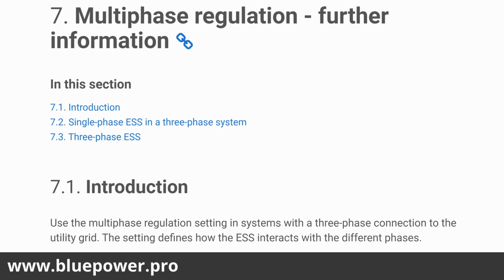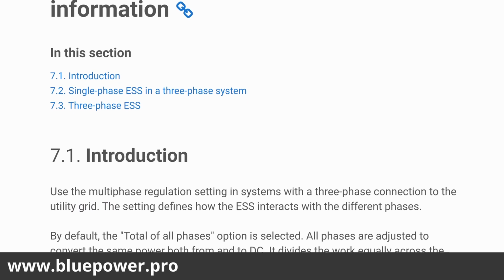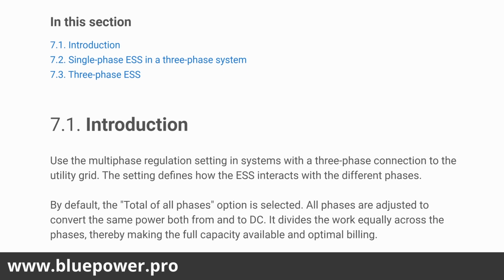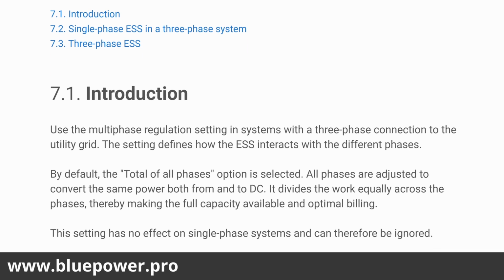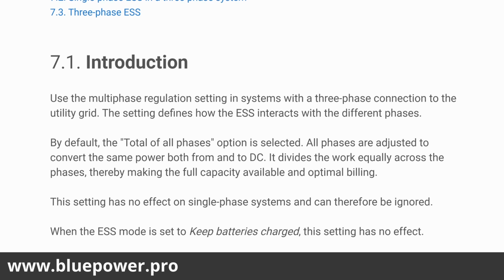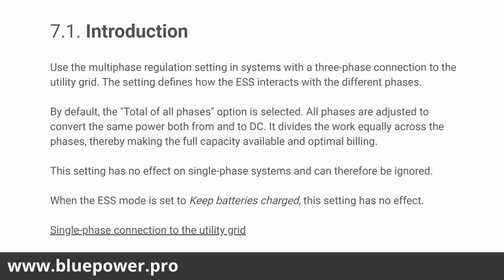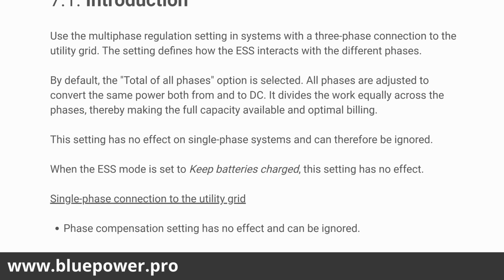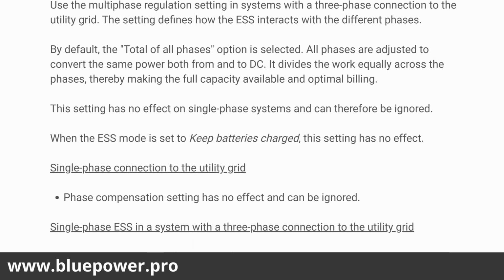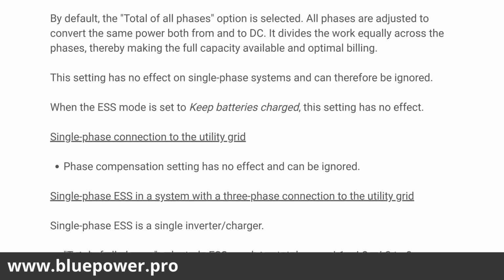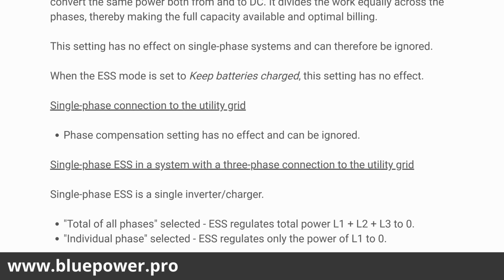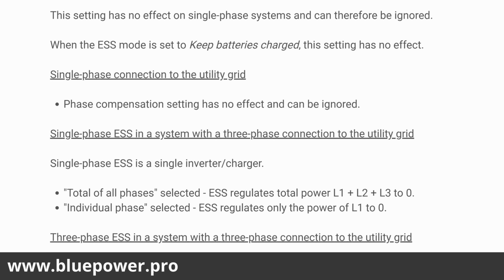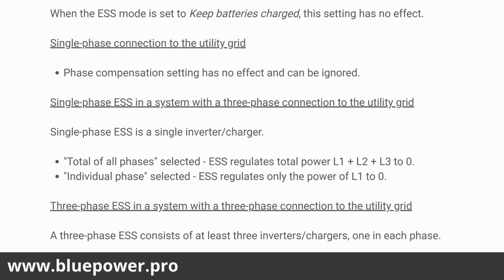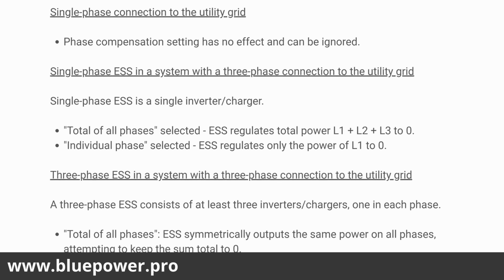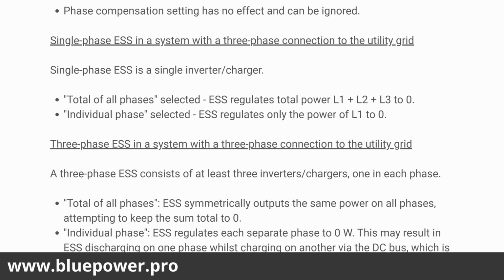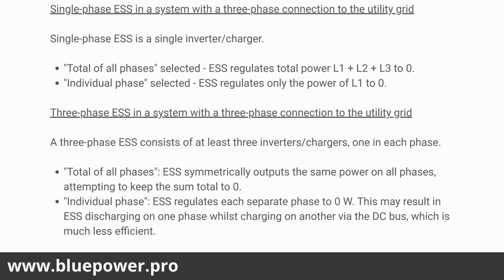And multiphase regulation, so that can be set as per individual phase or total of all phases. So that only applies if you've got a 3-phase system. What that does is if it's selected on per individual phase, it's going to keep each single phase at the consumption of your grid set point. So if you've got your grid set point at 30 watts, for instance, then it's going to have the total of those 3 phases not exceed 30 watts per phase.